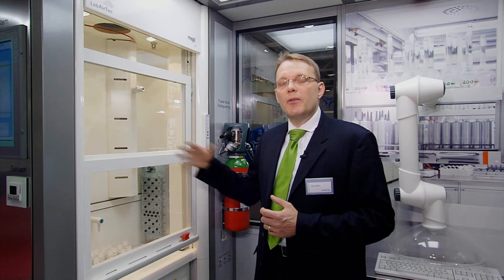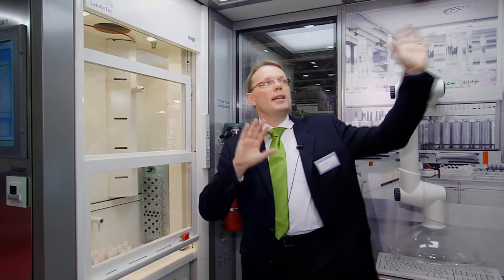In addition, if you have a fume hood with variable volume flow, it is key that the entire balancing of the laboratory's supply and exhaust air also fulfills the designed specifications. The adaptation of supply air happens in almost real time based on information from the fume hood. This reduces energy consumption and increases comfort by lowering noise pollution caused by the ventilation system.